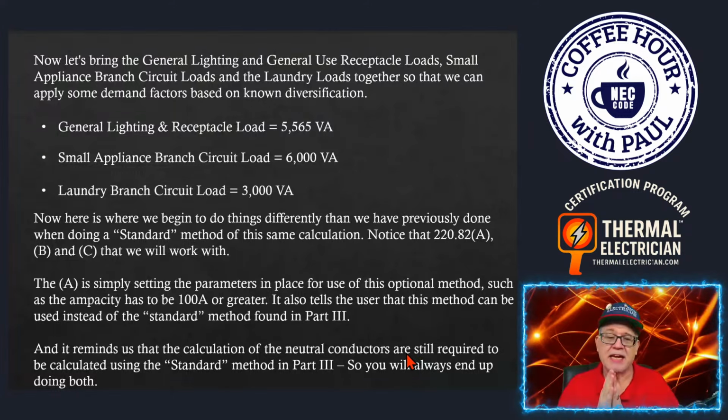But again, I'll give you a shortcut. If you're pulling conductors in and you size the conductors based on the load calc, if you don't make the neutral more than 2 sizes smaller, then it's essentially the same thing you would get inside of a pre-made cable assembly. You're going to be okay. If you buy SE cable, it's already made. Now, this is dwellings, not commercial, not industrial. Dwelling applications make life so much easier. So if I'm using 4/0 aluminum and that's my size, even if I put a raceway in there and I'm pulling conductors between it, right?